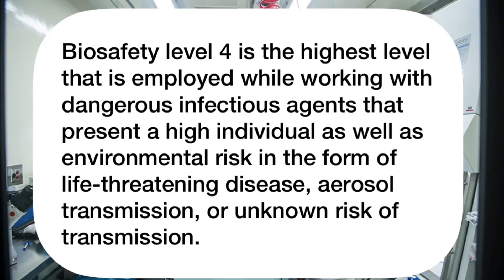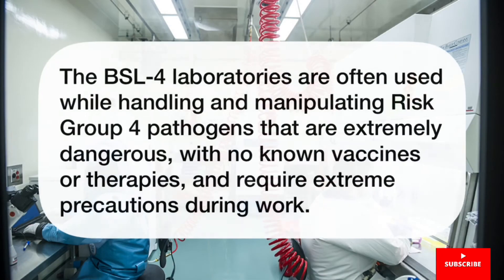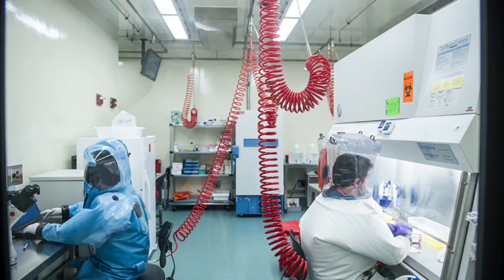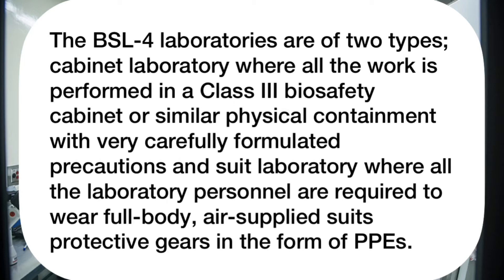Biosafety Level 4 is the highest level, employed while working with dangerous infectious agents that present a high individual as well as environmental risk in the form of life-threatening disease, aerosol transmission, or unknown risks of transmission. BSL-4 laboratories are of two types: Cabinet Laboratory, where all the work is performed in a Class III Biosafety Cabinet with very carefully formulated precautions; and the Suit Laboratory, where all laboratory personnel are required to wear full-body air-supplied suit protective gear in the form of PPEs.